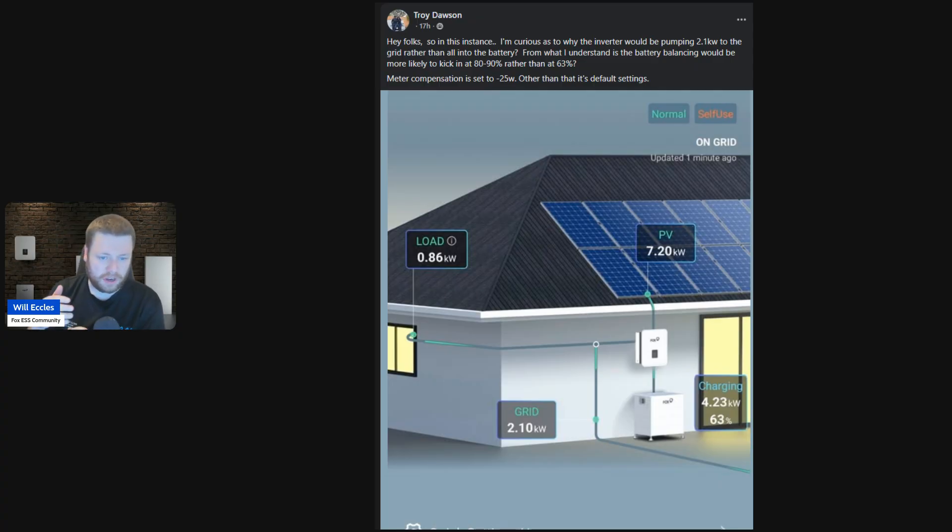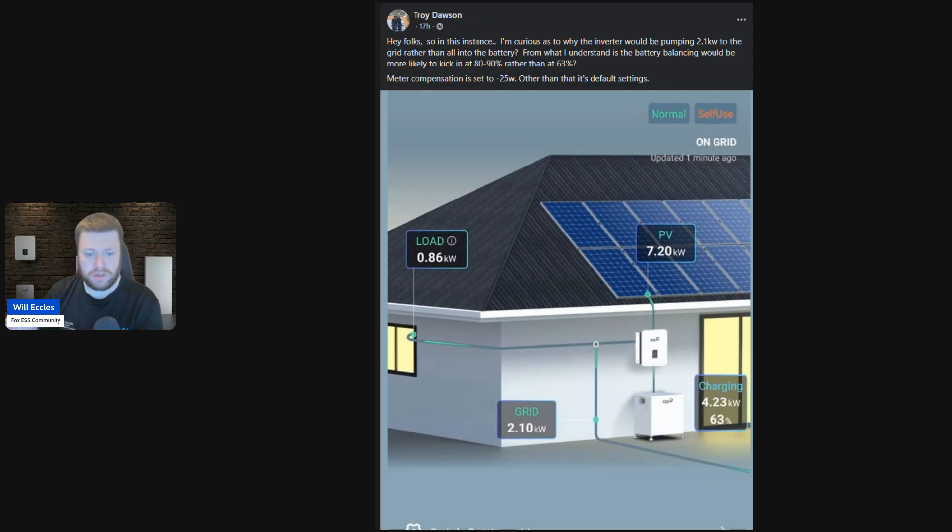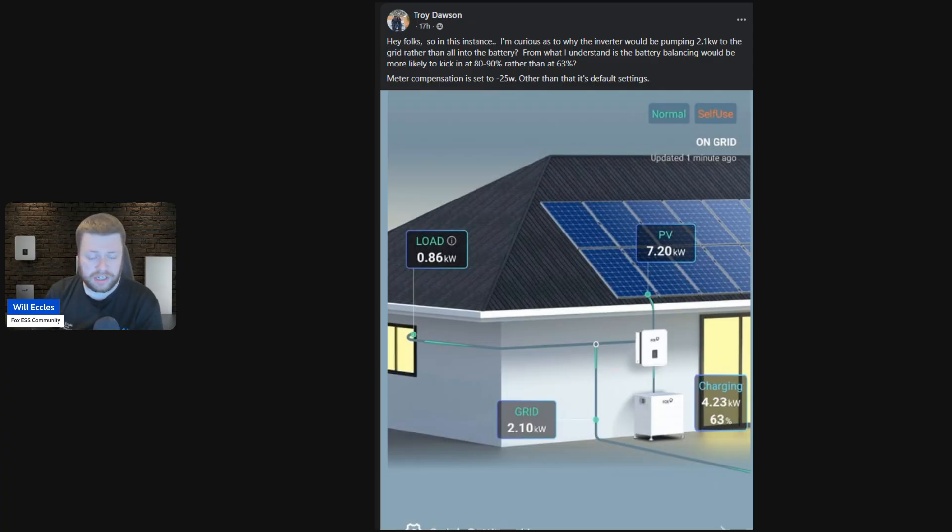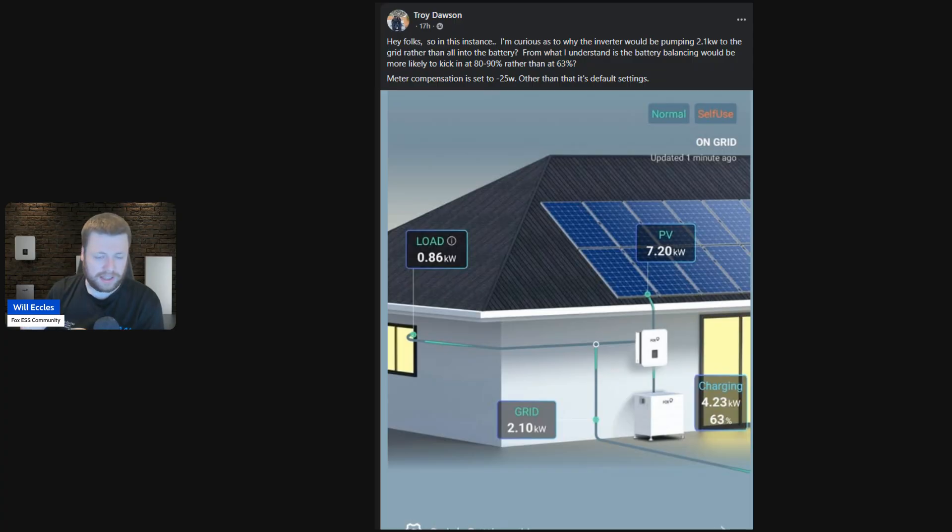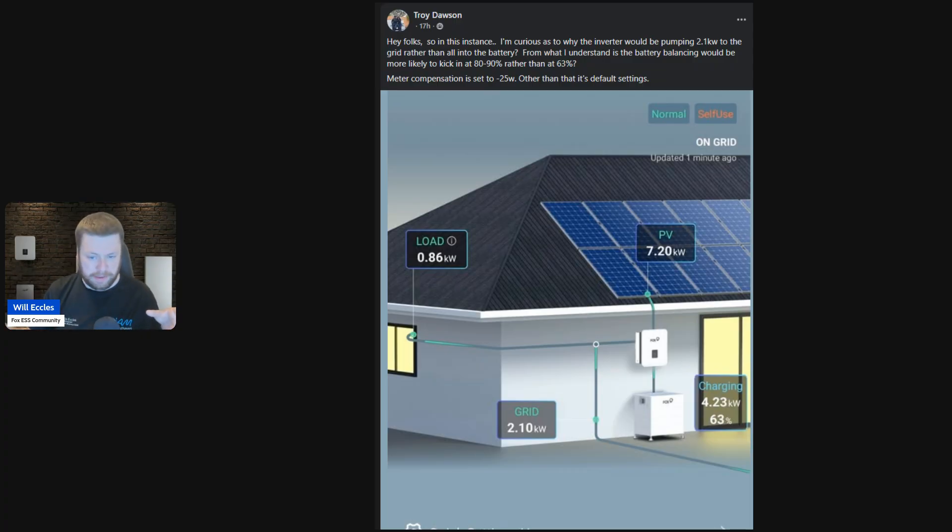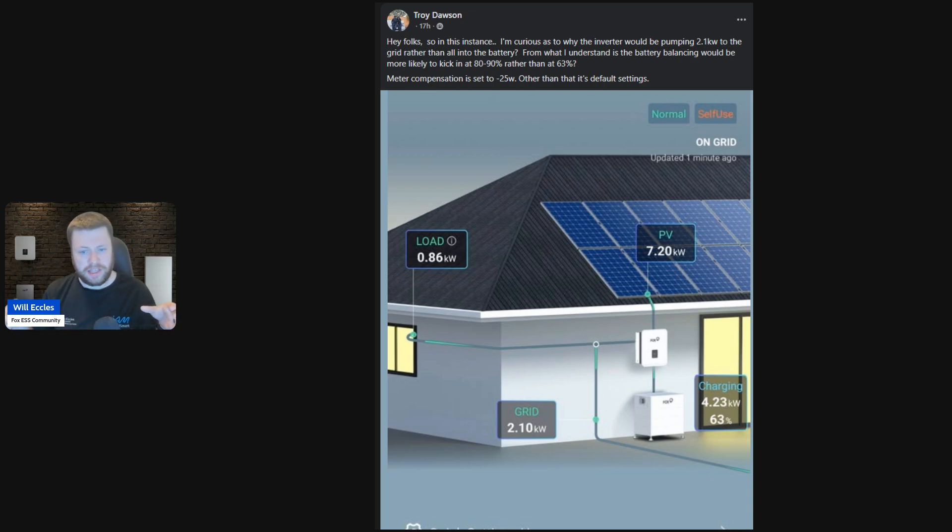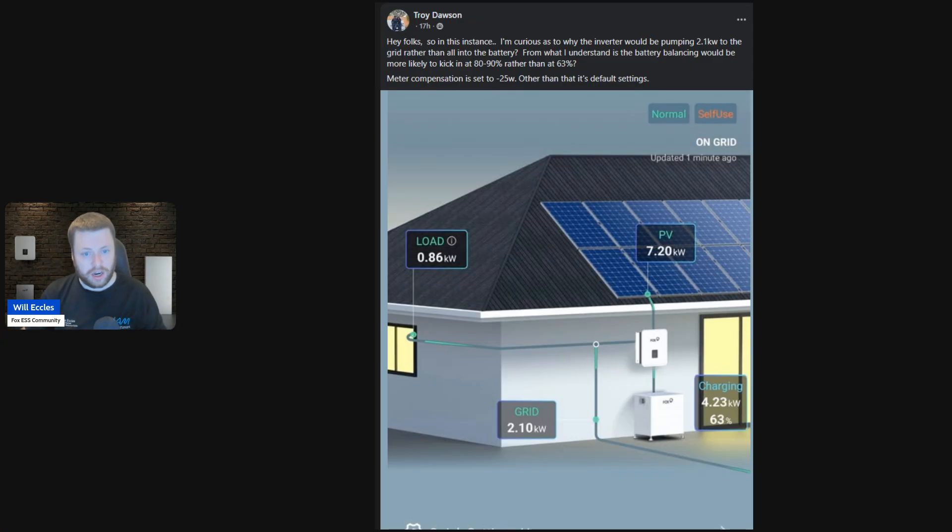I just thought we'd go into a little bit more detail about how your battery configuration and how that means that your voltage is typically higher, and then the charging and discharging amps is all controlled by the BMS. There are some configurations where you can't really improve this, and that's in configurations like the EP batteries. They're those square wall mountable ones. They are a set voltage as they come. When you add more EP batteries, you add more capacity, but because they're parallel connected, not serially connected, the voltage doesn't go up with every battery that you add of the EP range. Unlike the EQ and the other batteries, whereas you stack more batteries, your voltage increases.